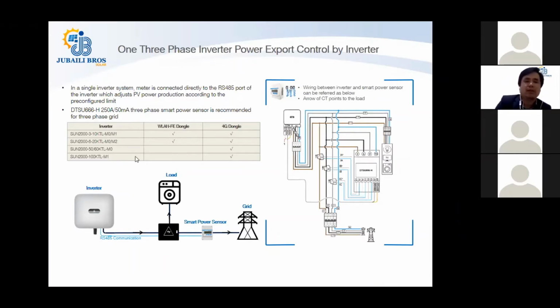So again, we have the option of using the DTSU, which is a Huawei power meter, and this Huawei power meter can be used up to a maximum of 170 kilowatt PV system. For a PV system larger than that size, you will need to look at one of the Huawei whitelisted power meters.